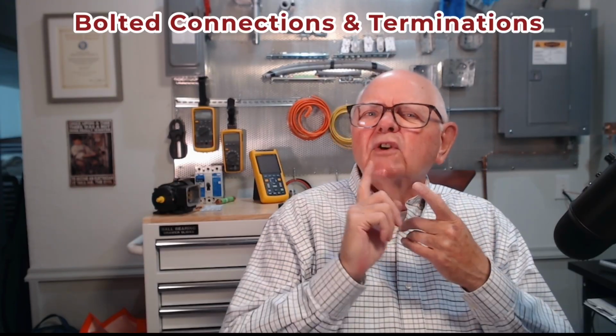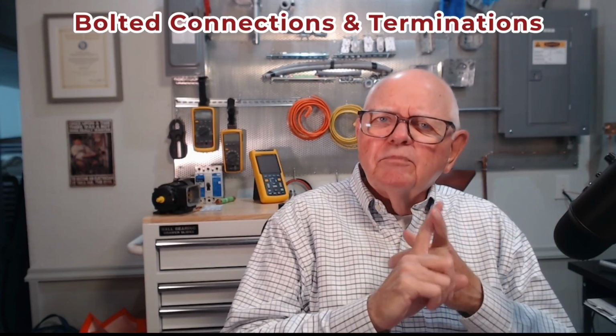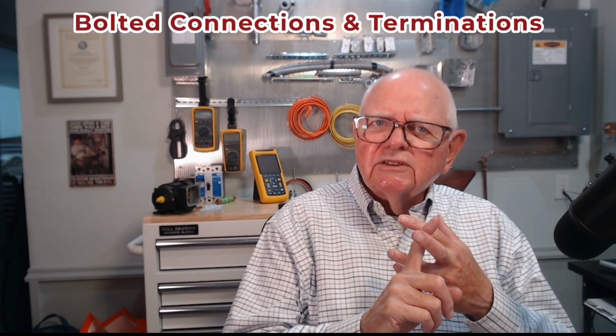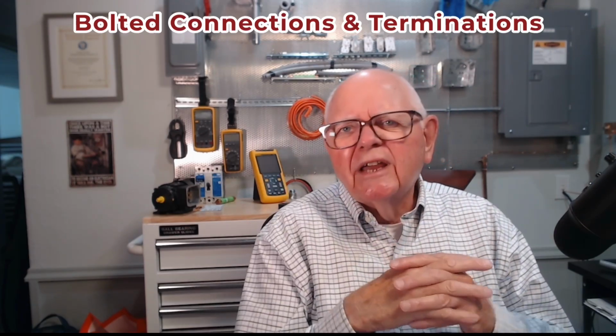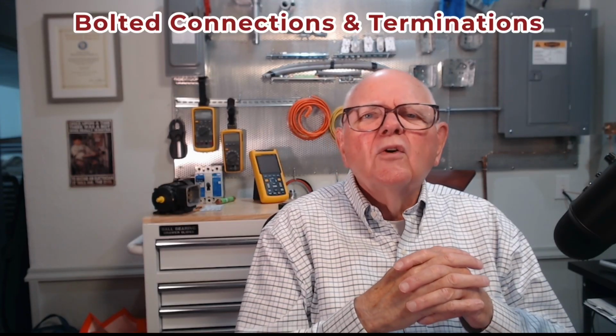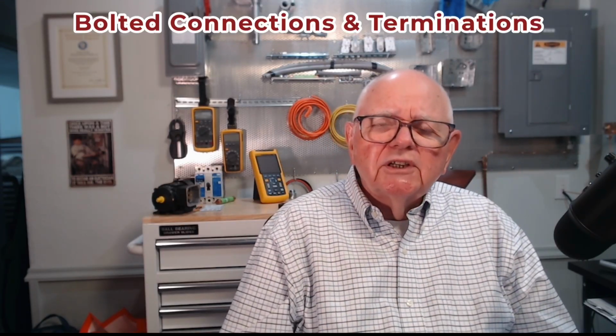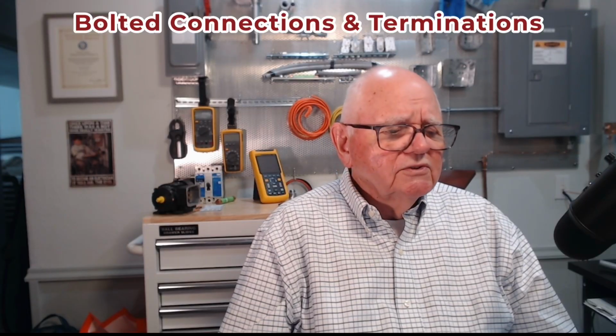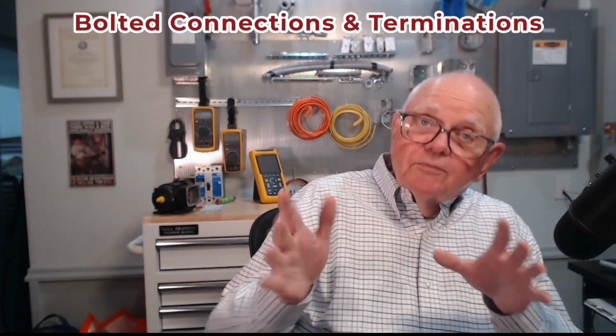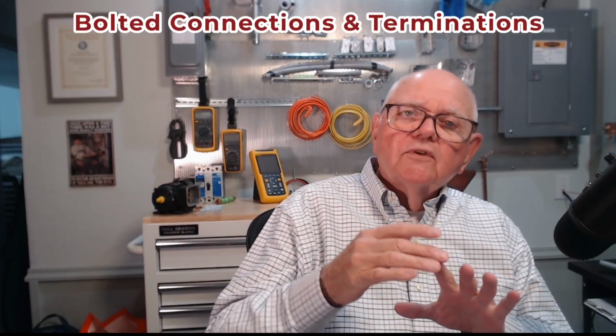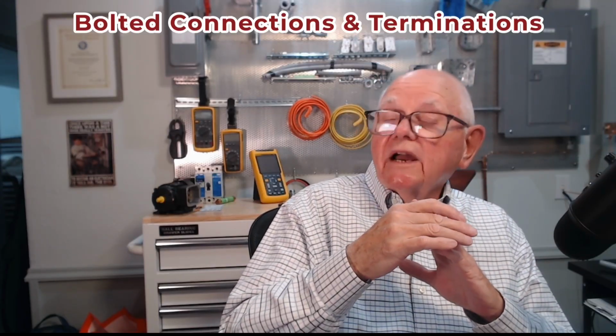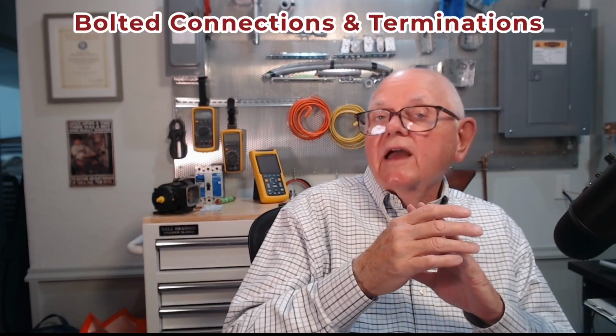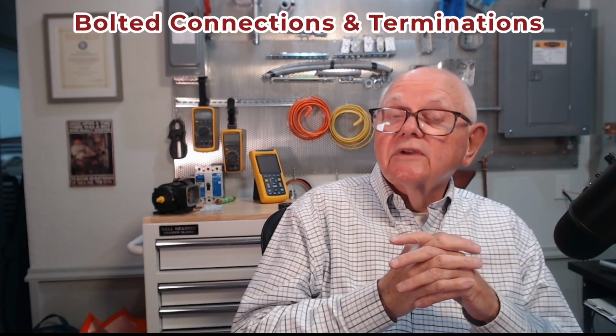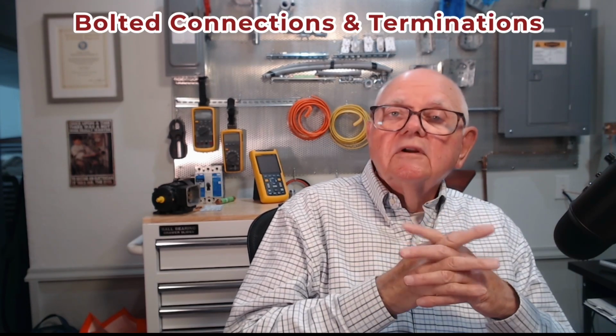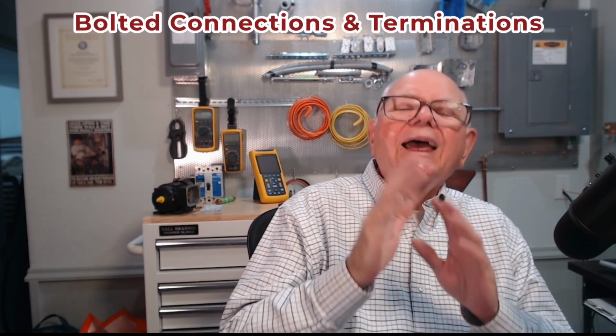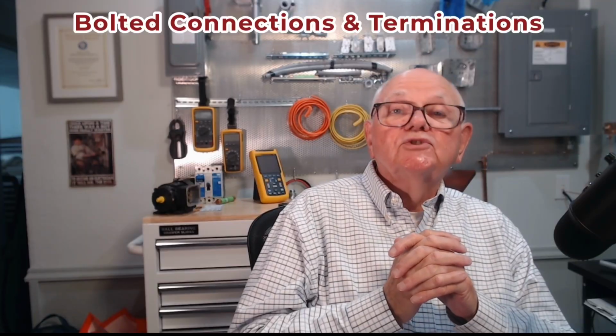And once again, we'll probably use those micro-ohm readings on things like switchgear bolted connections, bus bar bolted connections. Inside things like panel boards or disconnects and so forth, there we're typically going to use whatever the torque specification is that the manufacturer requires us to apply. Alrighty? So that's bolted connections then, really. We have our infrared thermal sensors. We can measure the micro-ohm reading across the bolted connection if that's applicable. Or we can take a calibrated torque wrench, screwdriver, whatever, and go in there and retorque that terminal at 90% of whatever that original installation torque value was, okay?